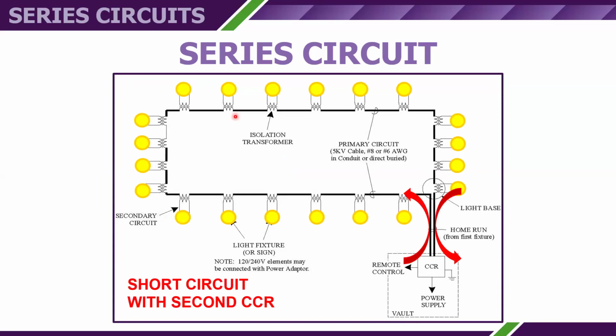What happens if we get a shorted output on our circuit with another constant current regulator? Power could be off on this circuit's constant current regulator, and a different constant current regulator could be coupled to your circuit. If the respective circuit's constant current regulator is off and the lights appear on or dim, check the circuit with a true RMS ammeter. Circuit could be coupled to another circuit that is energized.